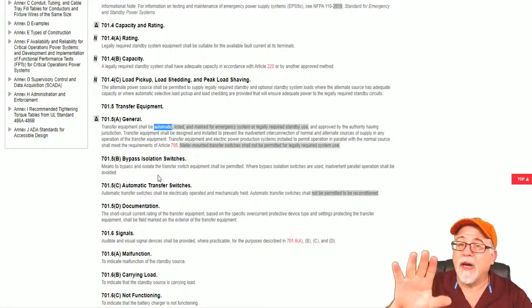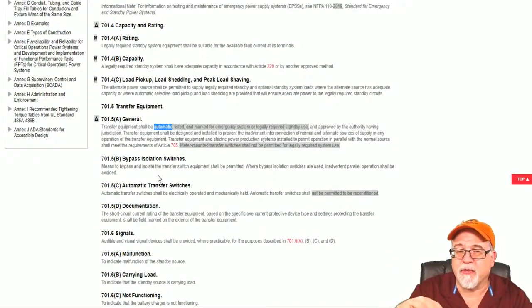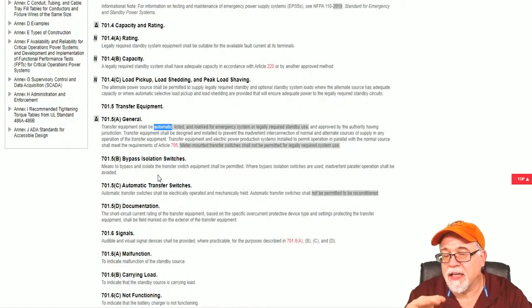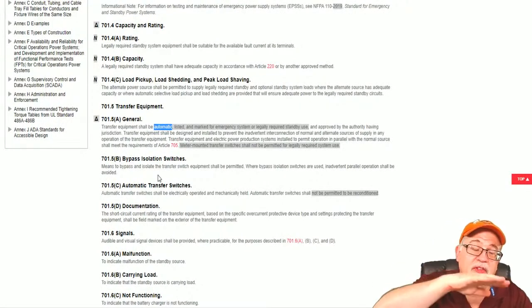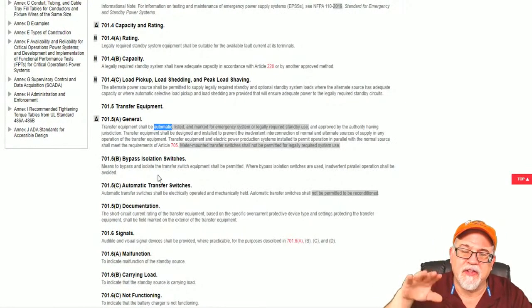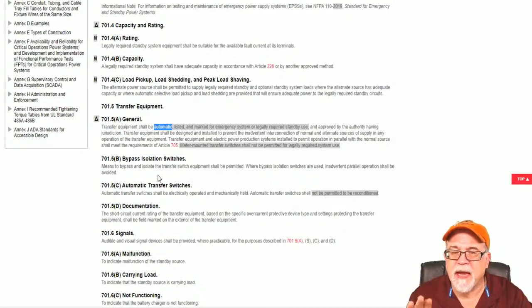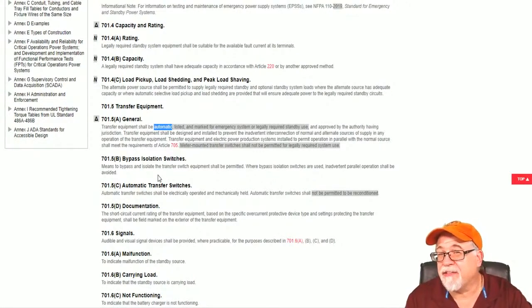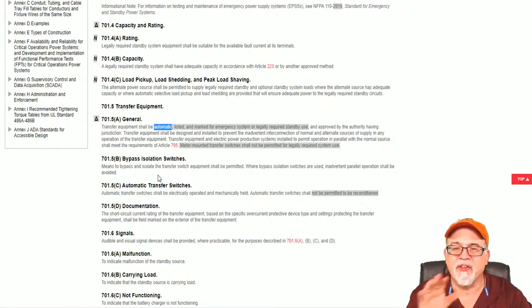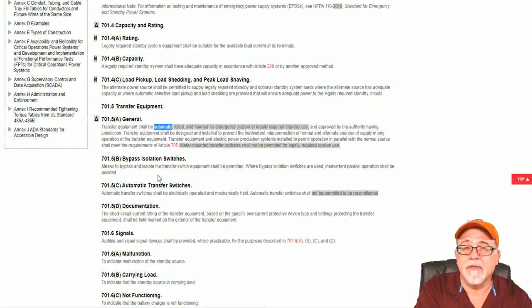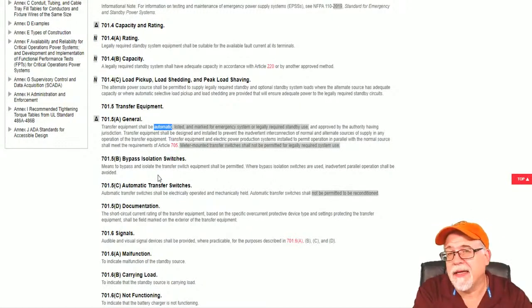Now, what's different about a transfer switch for legally required versus emergency is that typically the same automatic transfer switch for legally required also has to be marked for emergency systems as well, and it usually will be.